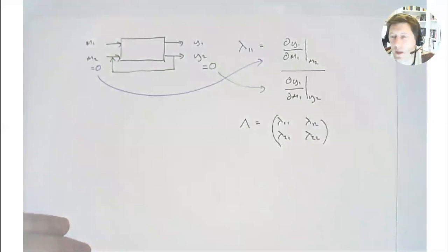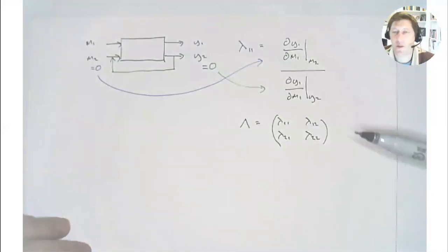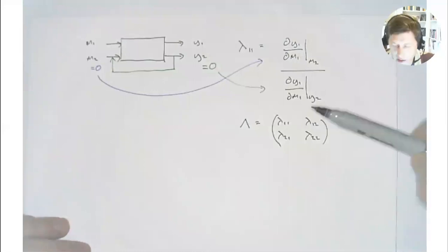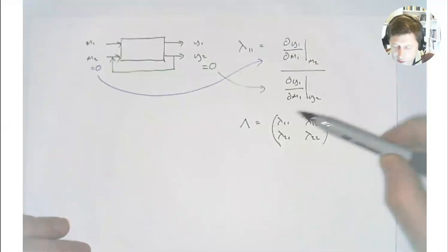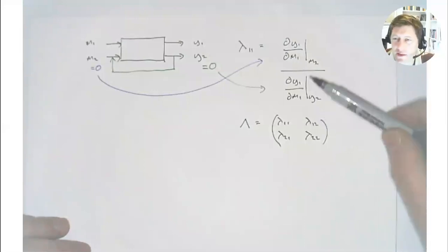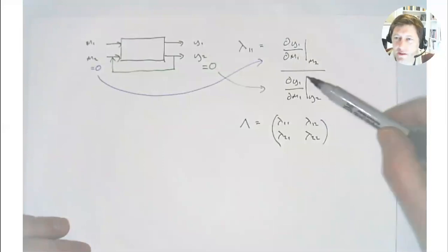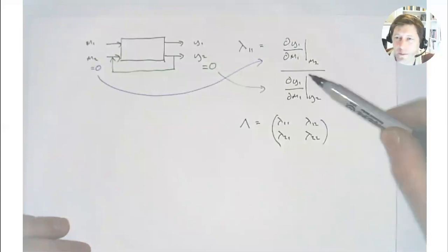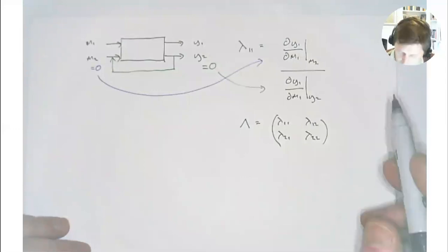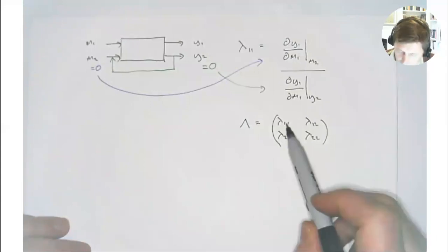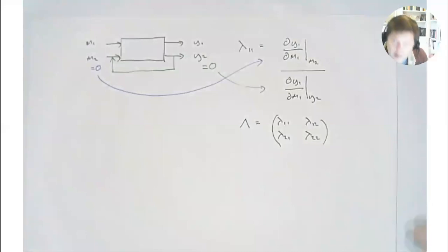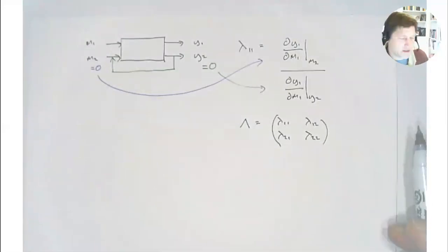And then this is a tool for working out the most appropriate control loops to make. And obviously, if these are equal to 1, then that's great. That means there's no effect from the interaction and the cross-coupling. And so we can make our array, and then we can look for possible values where lambda is closest to 1.